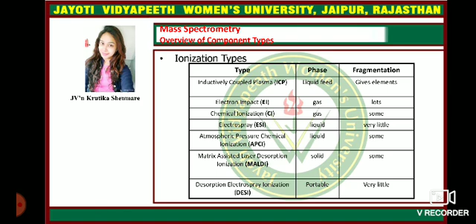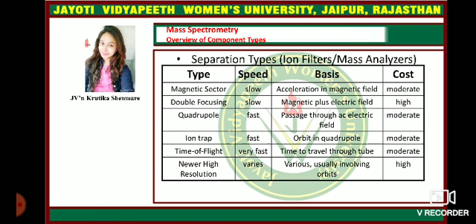The separation types are ion filters or mass analyzers. The magnetic sector has a slow speed, its basis is acceleration in a magnetic field, and it is of moderate cost. Double focusing has slow speed, uses a magnetic plus electric field, and is high cost. Quadrupole has fast speed, passes ions through an AC electric field, and is moderate cost. The ion trap is fast, its basis is orbit in quadrupole, and is moderate cost. Time of flight is very fast, measuring the time to travel through a tube, and cost is moderate. The newer higher resolution analyzers vary, including orbitraps.